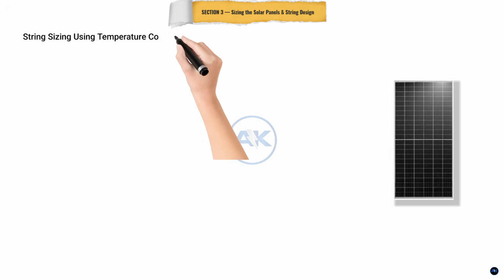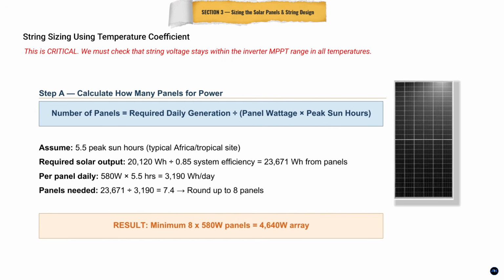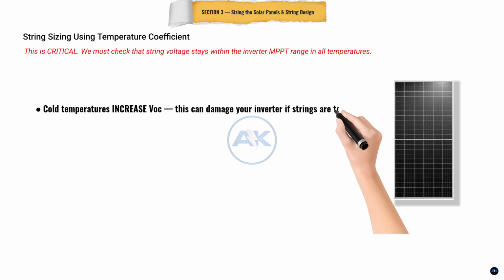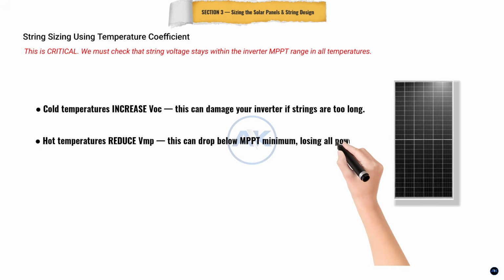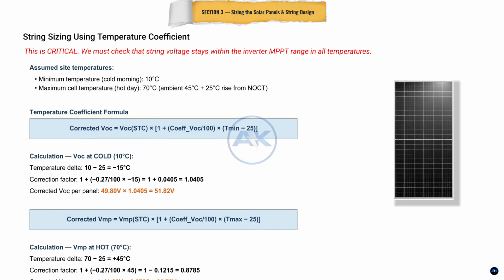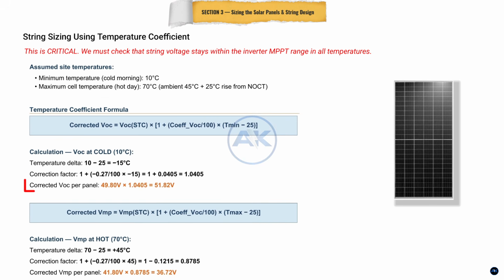But here is what most beginners miss: the temperature coefficients. The voltage changes with temperature. If you ignore this, you can destroy your inverter. Here is the rule: cold weather pushes voltage up, hot weather pushes voltage down. On a cold morning at 10 degrees Celsius, the VOC of each panel rises to 51.82 volts. That is higher than the panel's rated spec. On a hot day when the cell temperature reaches 70 degrees, the VMP drops to just 36.72 volts. We must account for both extremes when we design our string.